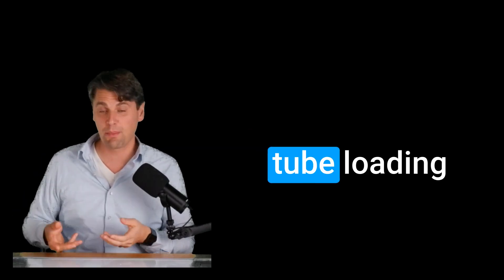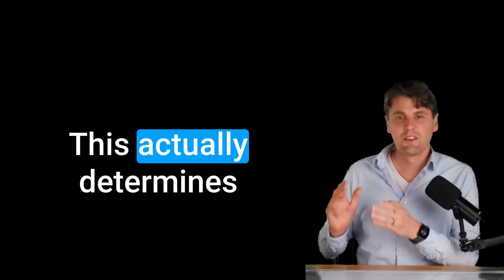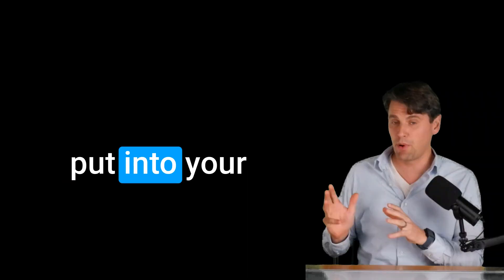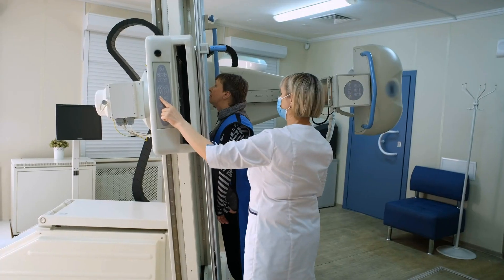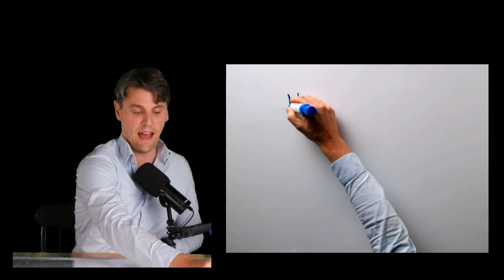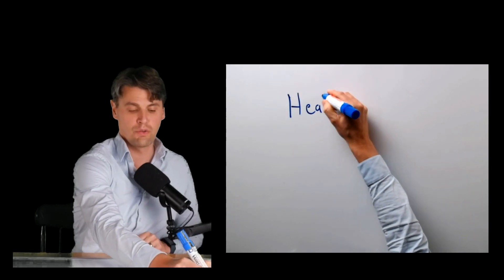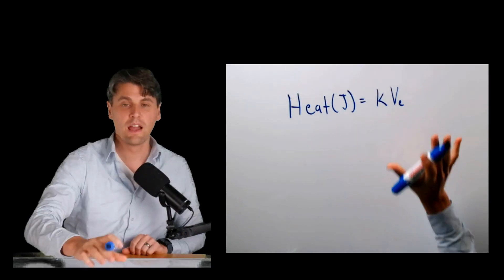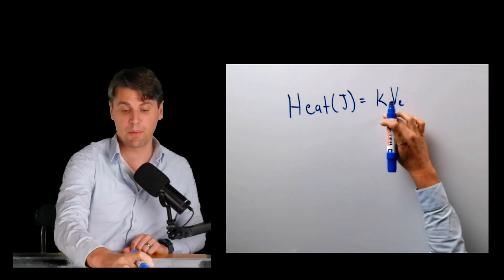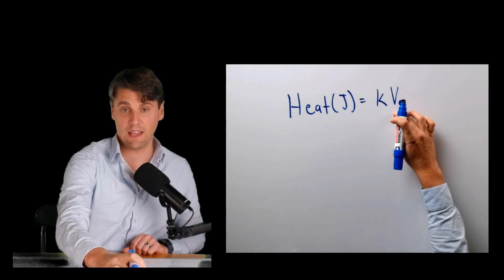All right, Red Nation, today we're going to be talking about tube loading. This actually determines how much heat you can put into your x-ray tube before you potentially would damage it. The units of heat that we have are joules. The heat that we deposit is actually proportional to the KV.